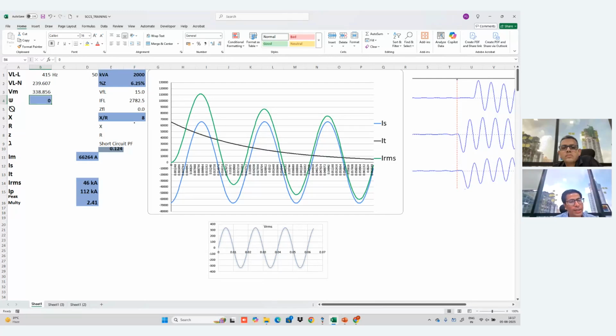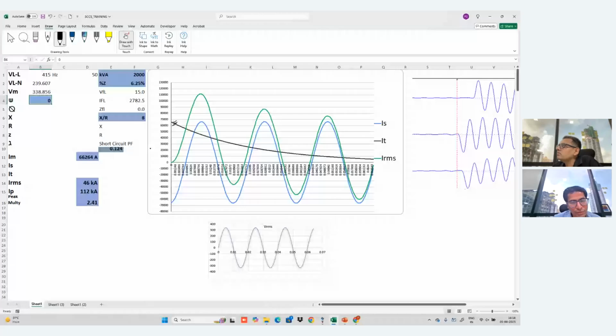So here, 2000 kVA with the regular 6.25 percent impedance, the X by R ratio is basically between 6 to 7 for the transformer. Now we'll see three aspects I told you I'd explain. The first is the point on the wave and what it will affect, the second is the X by R, and the last is this component, which I'll explain. Initially I have taken this as 0. Zero means the voltage is at 0 and the fault has occurred.